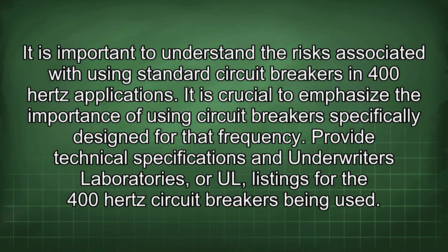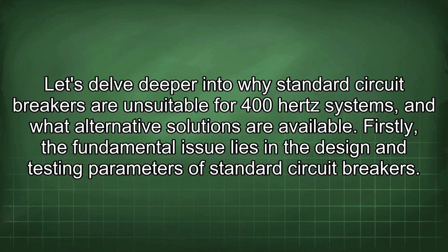It is important to understand the risks associated with using standard circuit breakers in 400 Hz applications. It is crucial to emphasize the importance of using circuit breakers specifically designed for that frequency. Provide technical specifications and Underwriters' Laboratories or UL listings for the 400 Hz circuit breakers being used. Let's delve deeper into why standard circuit breakers are unsuitable for 400 Hz systems, and what alternative solutions are available.